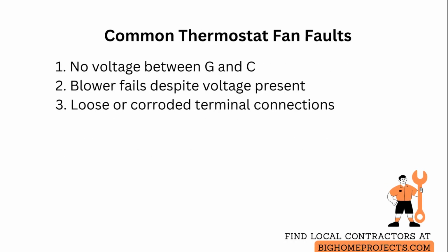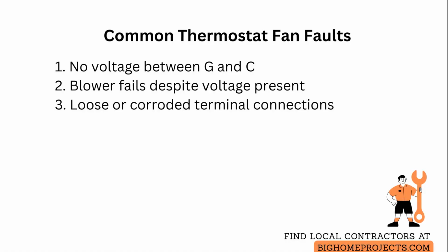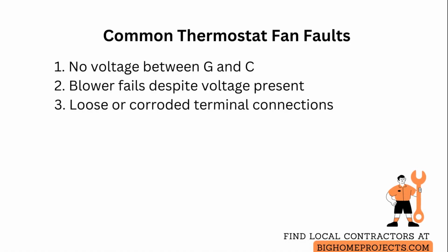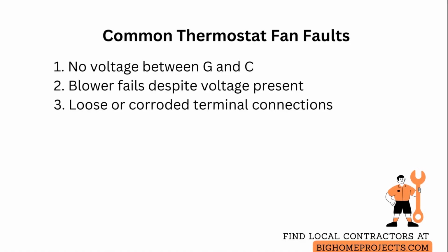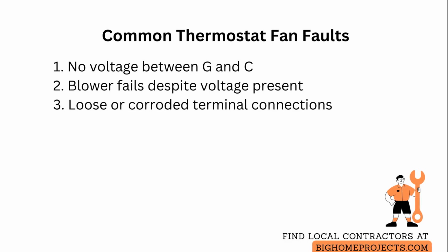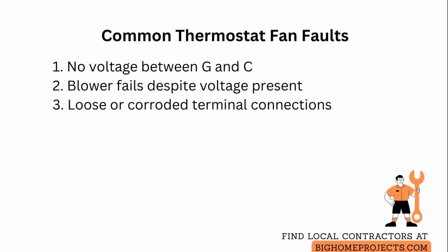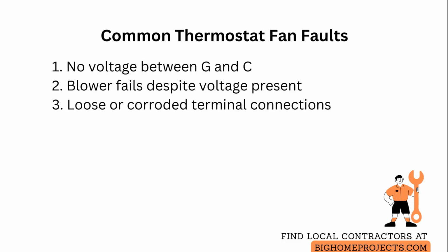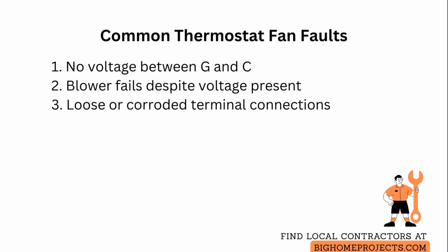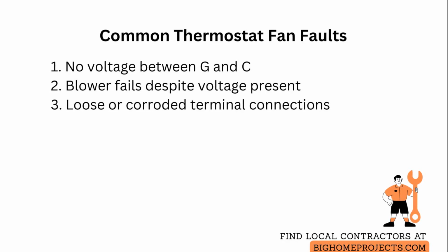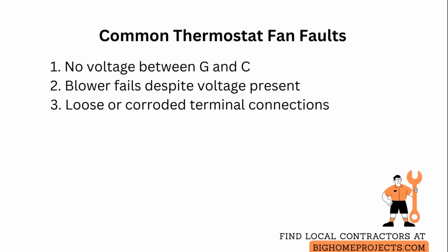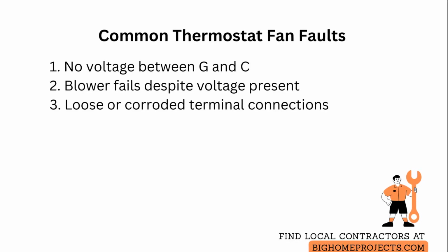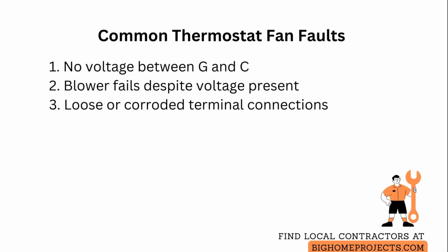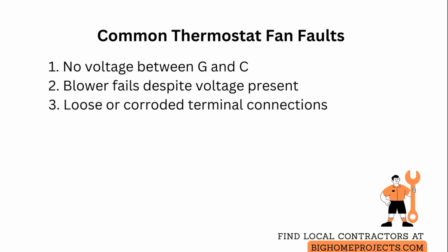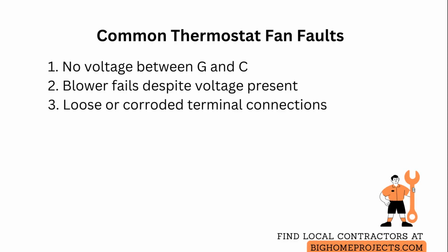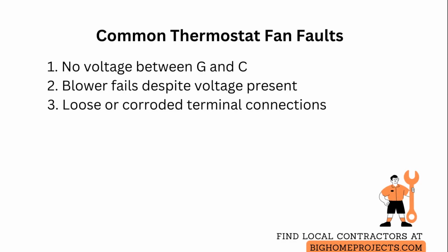Common issues include, first, no voltage between G and C caused by a failed thermostat, which is solved by substituting a known good thermostat or testing thermostat continuity. Second, voltage present but no blower operation due to a defective relay or control board, which is solved by testing the relay coil and replacing the board or relay module as specified by the manufacturer. Third, intermittent operation from loose or corroded terminals, which is solved by cleaning, tightening, and applying appropriate terminal protection and retesting under load.